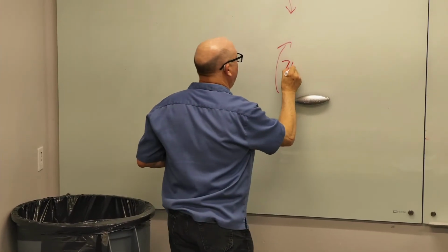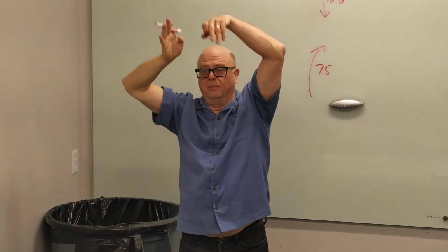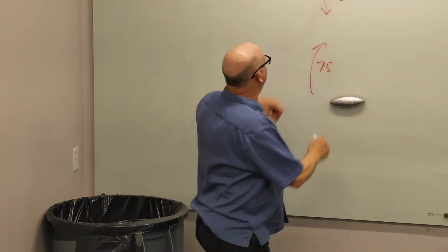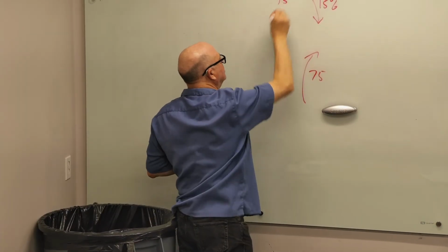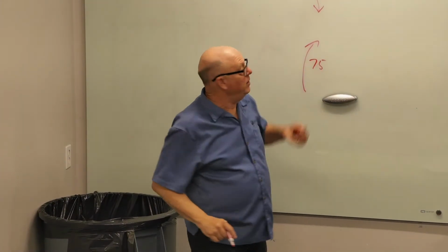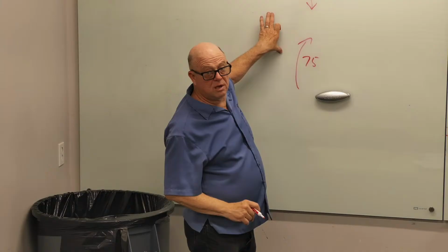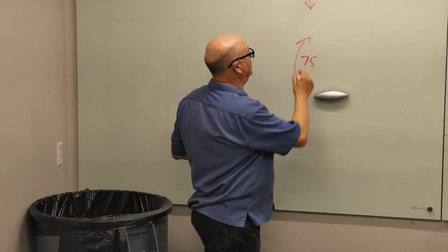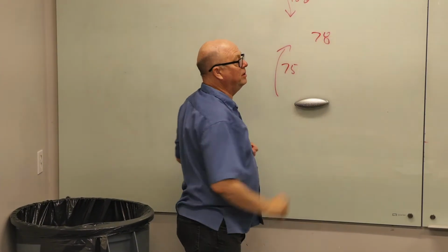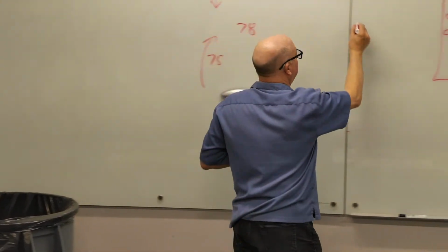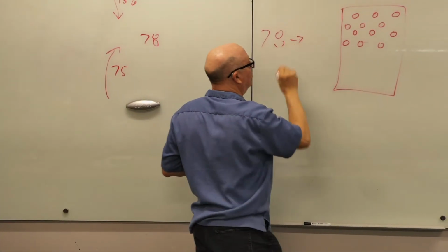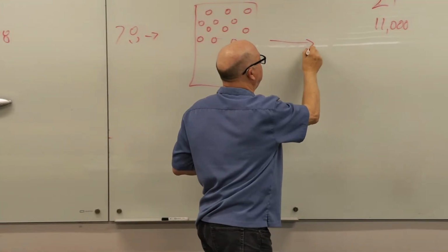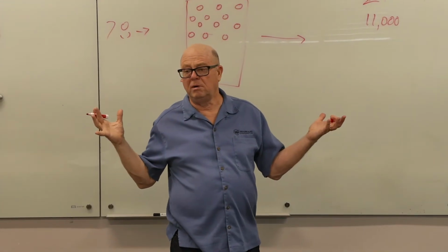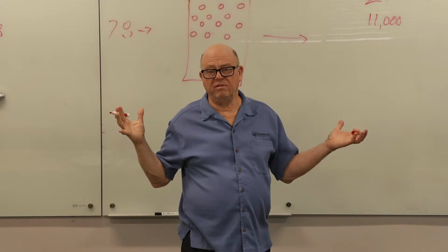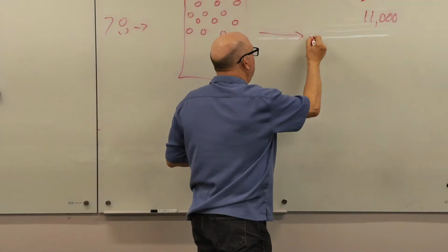So we got 75-degree return air up in the plenum. We're putting in air at 95, let's say, because it's hot outside. That's a 20-degree difference. And if it's 15% outside air, that means it's going to be 78-degree mixed air. So here we got 78-degree mixed air coming in, and what temperature do we want to make in a VAV system as a default number? Somebody please say 55. 55. Thank you.